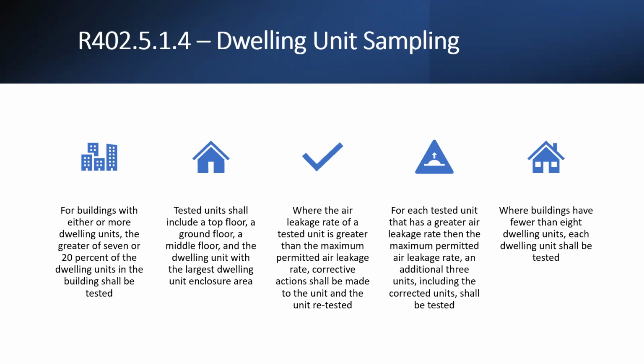It does not specifically call out mechanical ventilation, but some cities do go ahead and write a sampling protocol that fits the same thing we just read, also for mechanical ventilation. But since mechanical ventilation has to be tested in 2021, they're trying to get you to not have to test every single unit for mechanical ventilation, but you follow the same protocol. If one fails, it has to be corrected, and you add 3 more to the sampling testing package. So to do it that way.